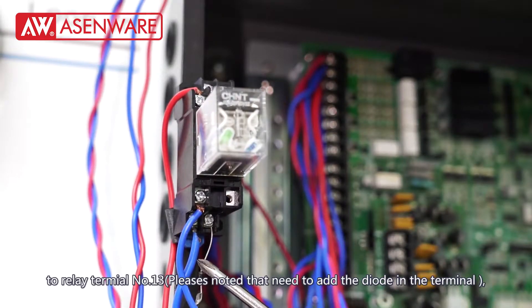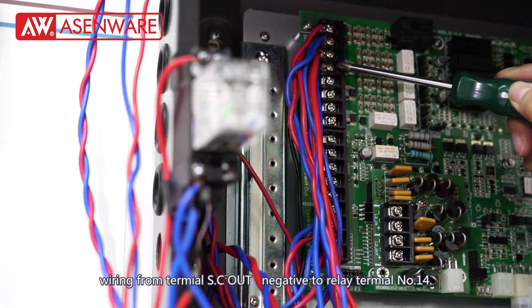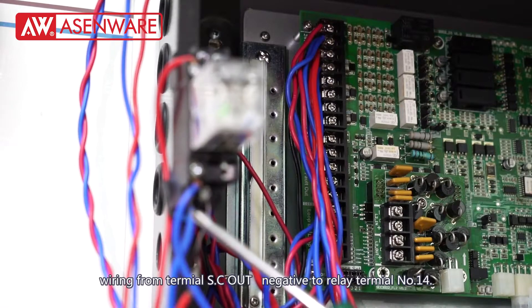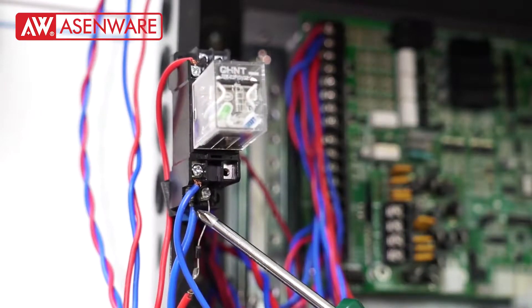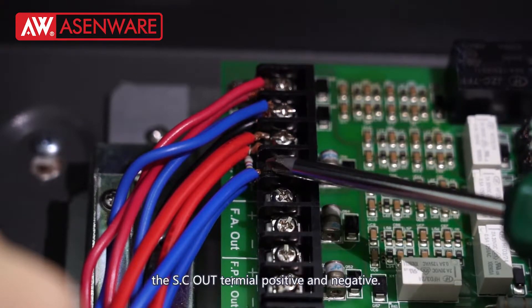Please note that you need to add a diode in the terminal. Wire from terminal S.C OUT negative to relay module terminal 14, and also add a 4.7Ω resistance in parallel between the S.C OUT terminal positive and negative.